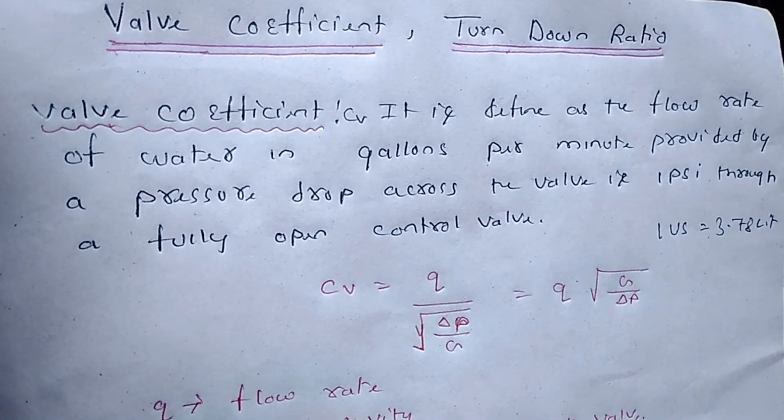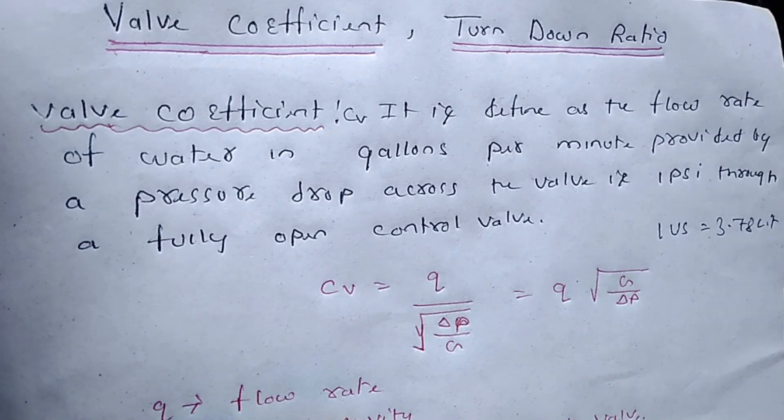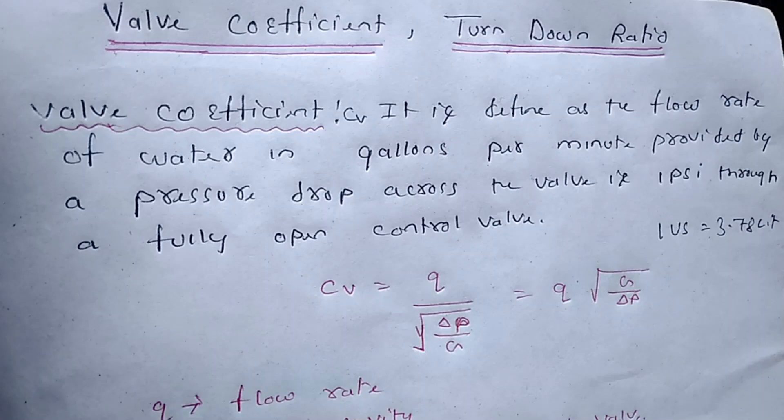So the number of U.S. gallons of water at 60 degrees per minute that flow through the valve with a specified opening, that is usually wide opening, and pressure drop across the valve is 1 psi. So this is valve coefficient.